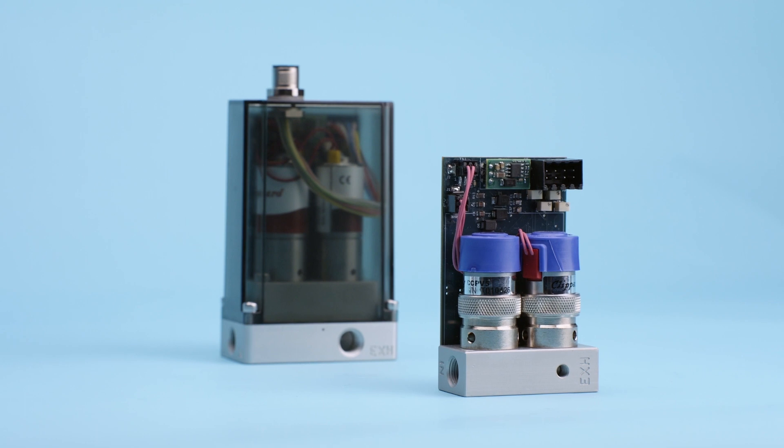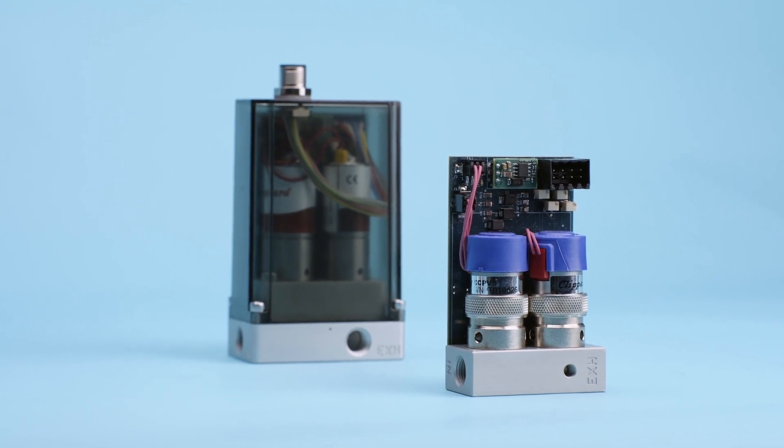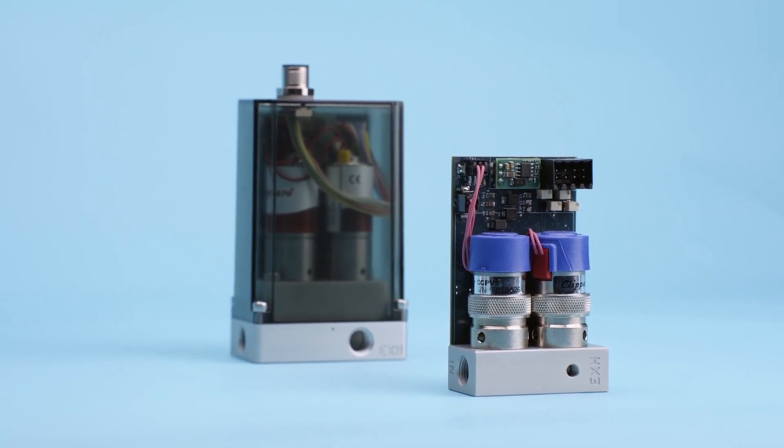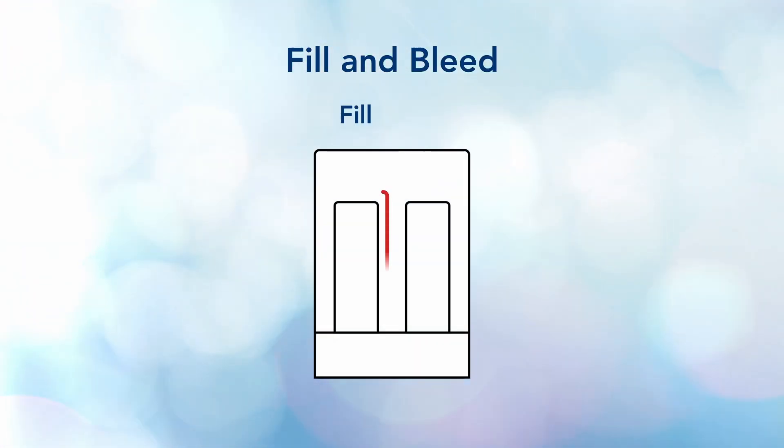Let's hone in on how to properly plumb the Corda CPC series when working with vacuum. The Corda CPC is a fill-and-bleed electronic pressure controller. One proportional valve is dedicated to filling, the inlet, and one proportional valve is dedicated to bleeding, exhaust.